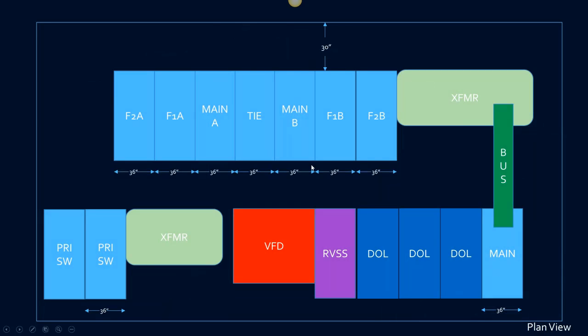Okay, so this is a plan view of what our electrical room might look like based on the one line that we were just studying. We have a lineup of medium voltage switchgear here, and many sections of medium voltage gear are 36 inches wide. We have a transformer, our 3000 kVA, that's transforming, say, 12,470 to 4160 for our medium voltage motor controls. And over here we have one of the unit substations.